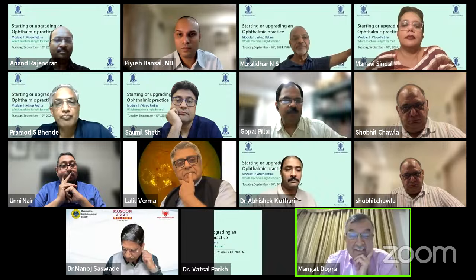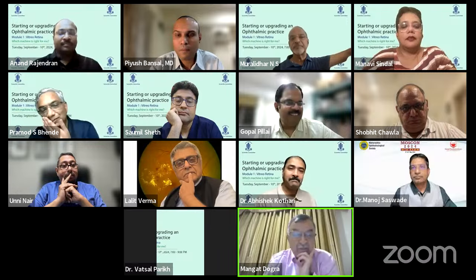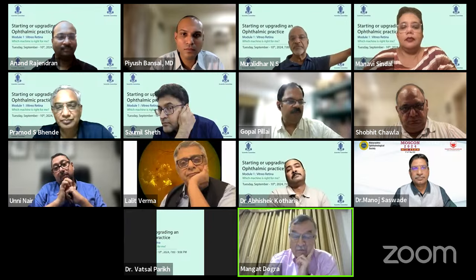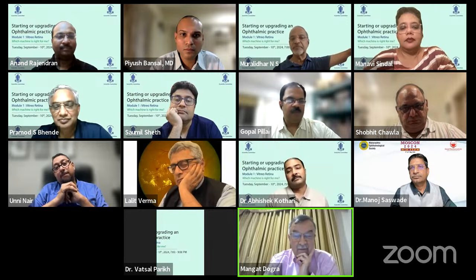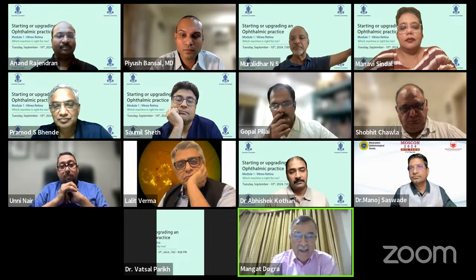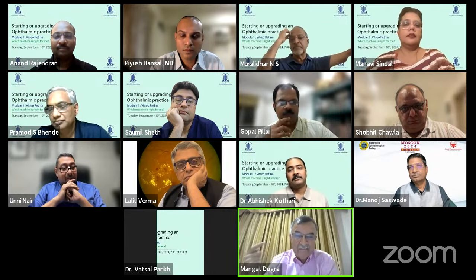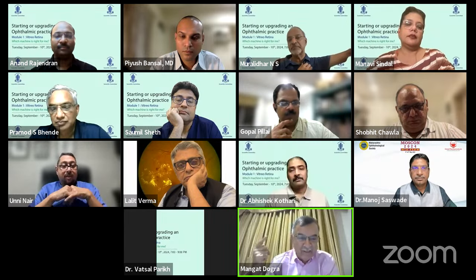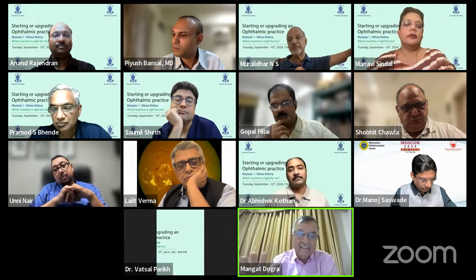I can answer this question. All the multi-spot won't last that long. That is what our experience was in the institution. But the single spot, they are workhorse. Of course, it takes more effort and more time, but they would last absolutely for a long time. And another thing I would like to say: have a laser which can work everywhere. Suppose you can afford only one laser and you want to do everything, the slit lamp, LIO, ROP, carrying it, laser barrage, everything. I think any 532 laser you buy will do everything.